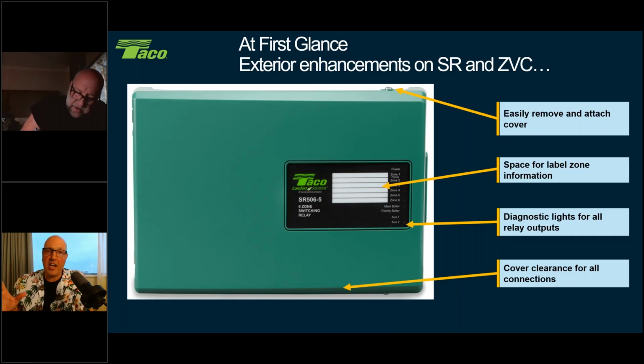I know a few of you guys out there that have put these in and the cover didn't fit after you wired the whole thing up and realized that you needed to put a washer or an extra nut on that BX connector to bring it away, or you broke out the grinder and you cut the cover so it would clear because you didn't want to have to rewire anything. We redesigned it because it was a couple of manufacturers, not all of them, a handful of them still worked with that cover, but we wanted to make sure we had clearance for everybody. So that was a big change. I'm really happy with that change that we did there too.